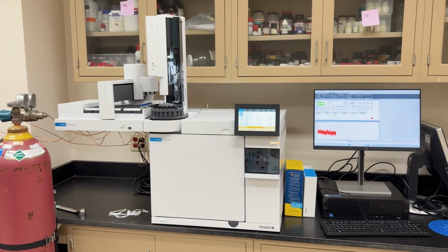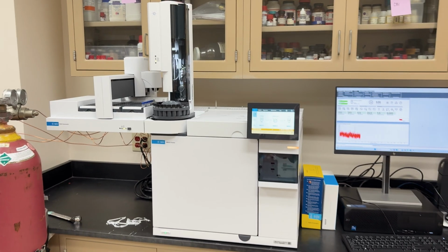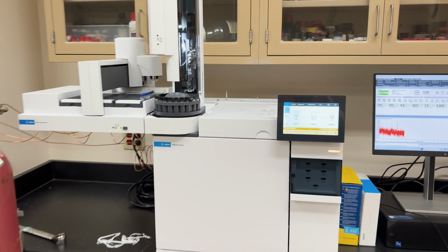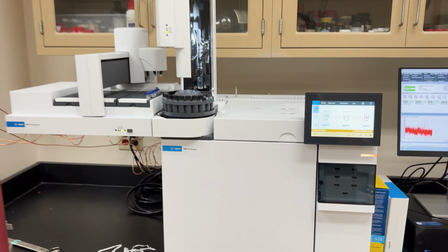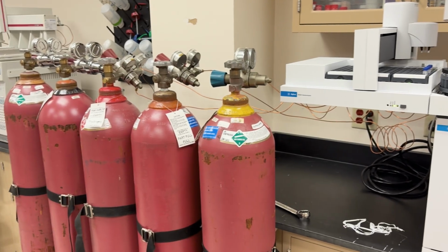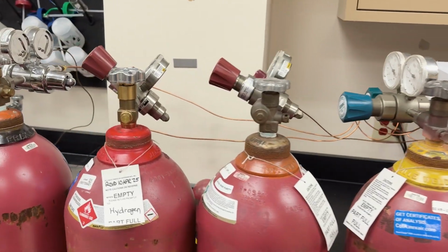The intention of this video is to get you started on the GC-FID we have, which is an Agilent 8890 GC-FID, and it's running the MassHunter software, which is usually for GCMS, but we're running it on the GC-FID.